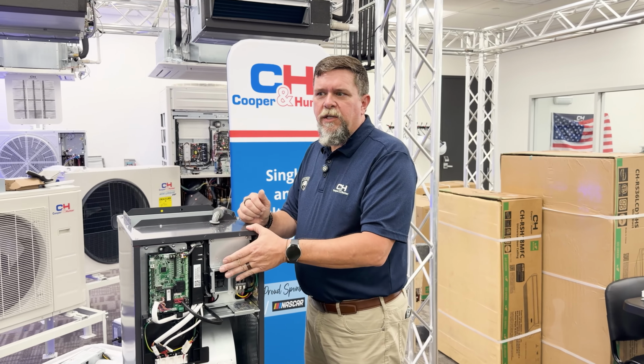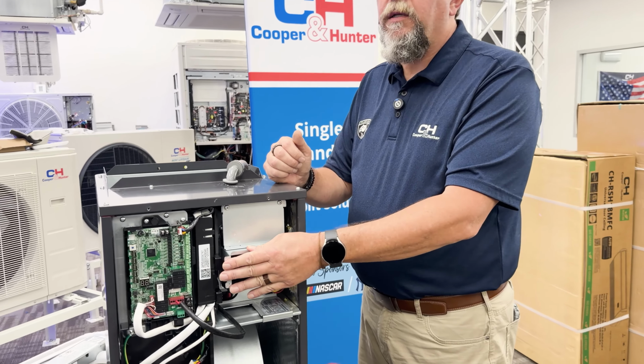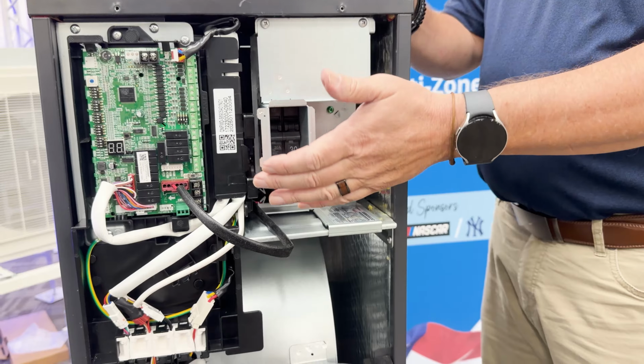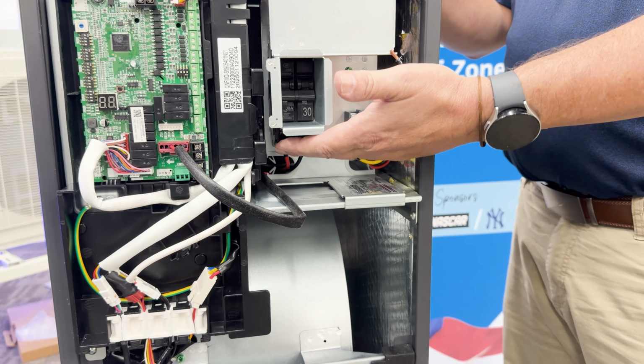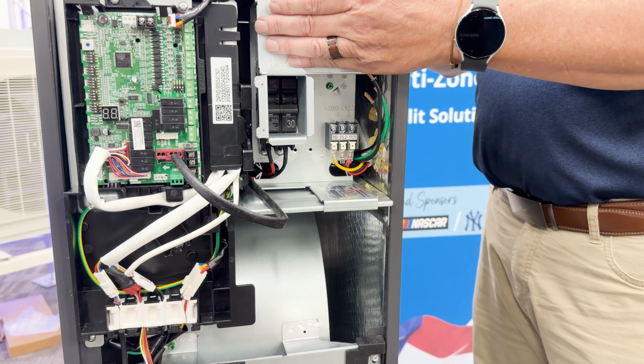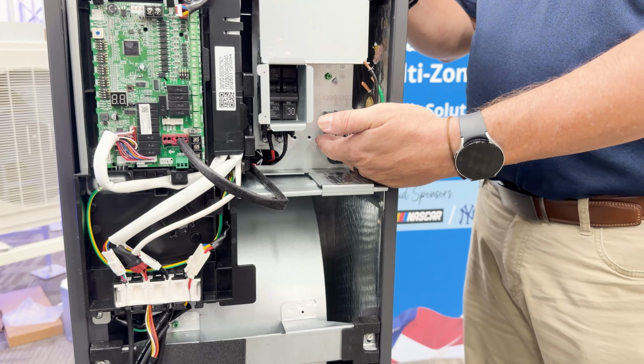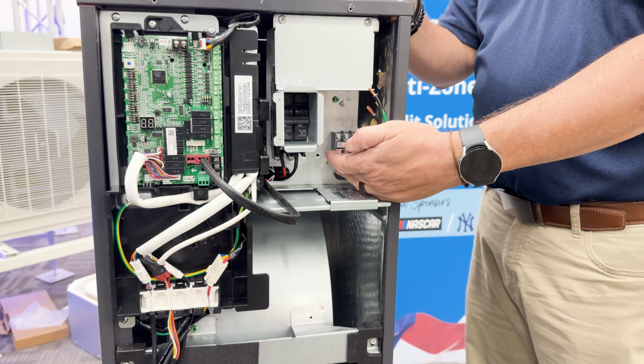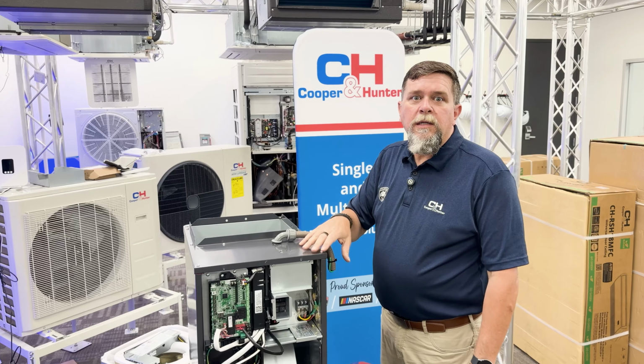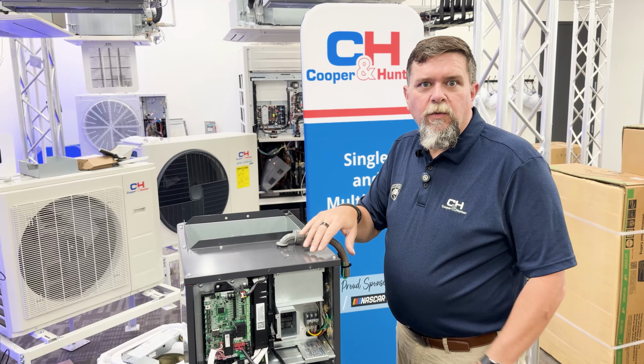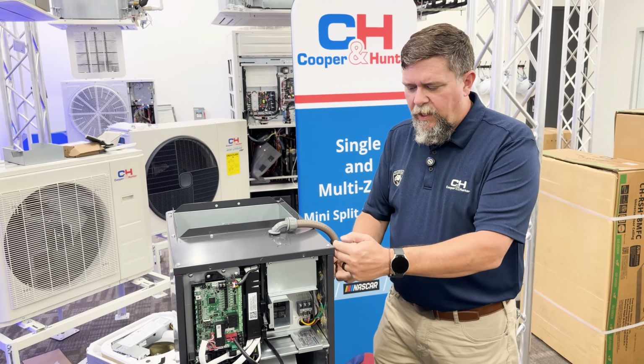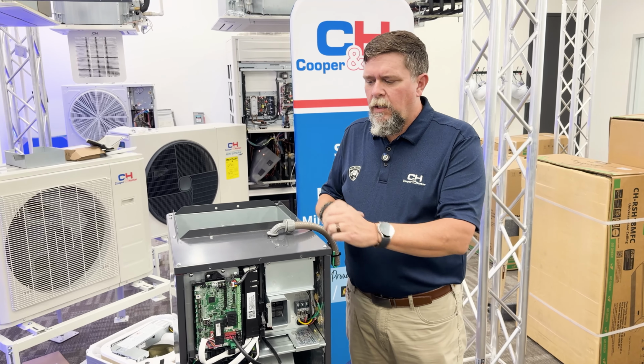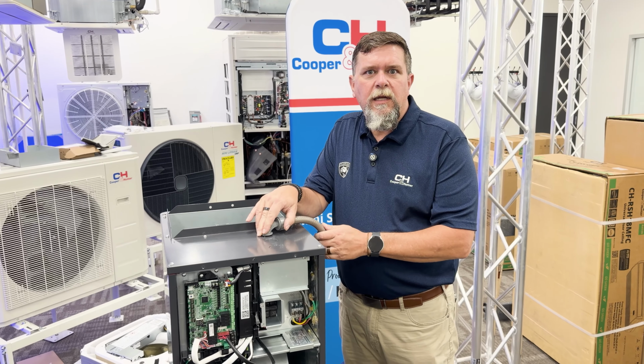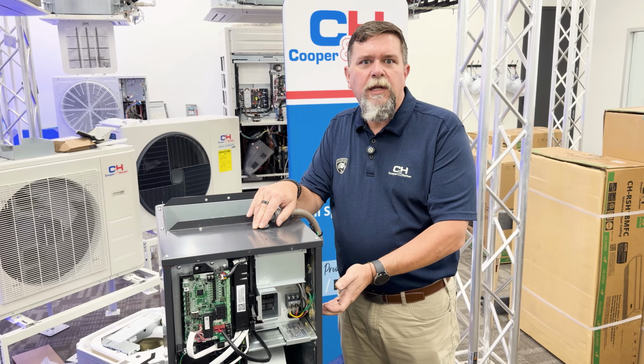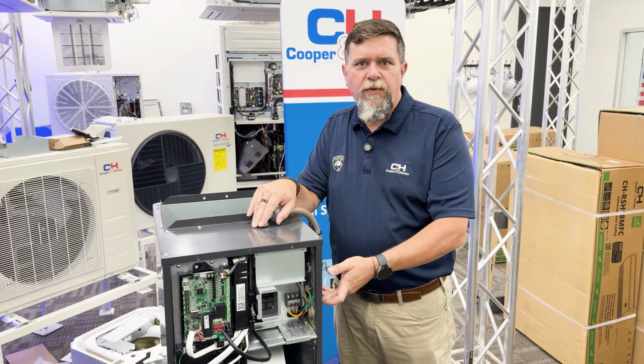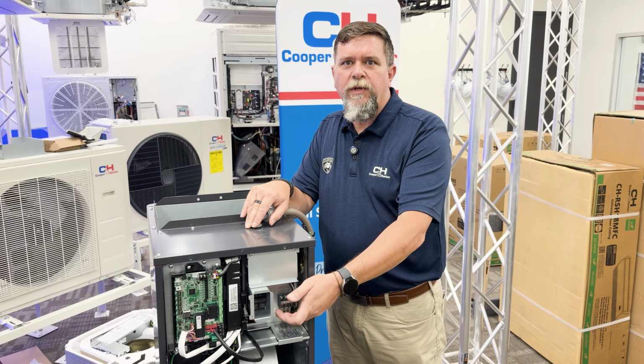When installing the electric auxiliary heat kit, the wiring is important to understand. It is two separate power sources. We'll have a power wire that wires to the circuit breaker that acts as an on-off switch for the auxiliary electric heat strips, and then a separate power source here on L1, L2 just for the air handler itself. To assist in wiring up the unit, we do have a series of knockouts on the top as well as on the side of the cabinet. I'm choosing to use the 1/2-inch knockout today for power wiring for my demonstration, and I'll use one here. The other 1/2-inch for the fittings that I do have for the power wire just for the air handler itself.